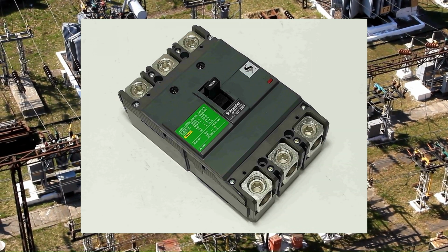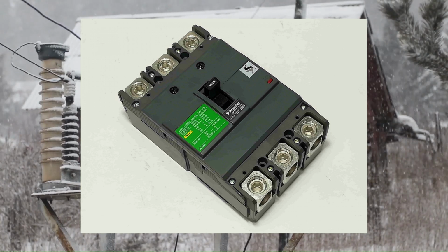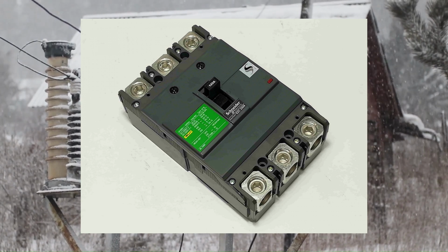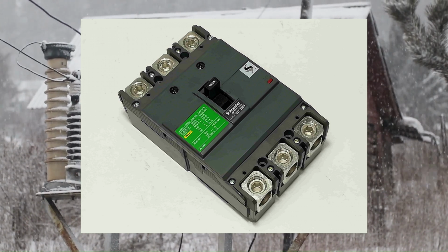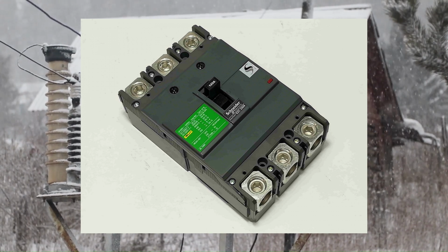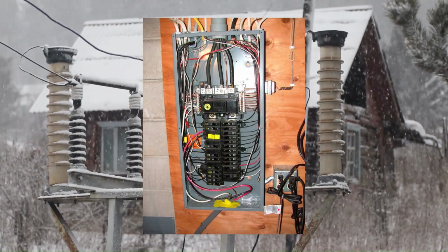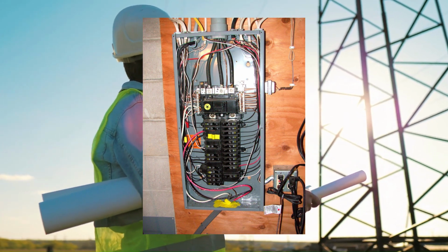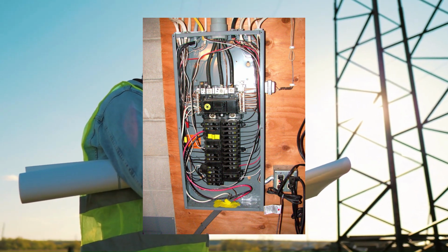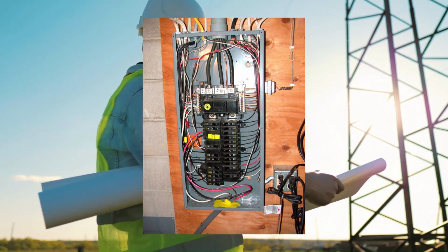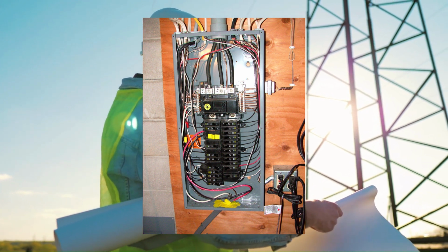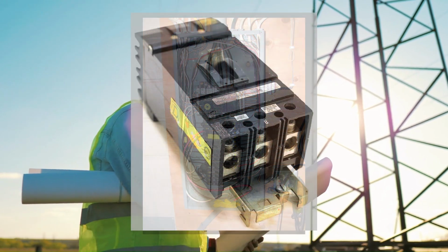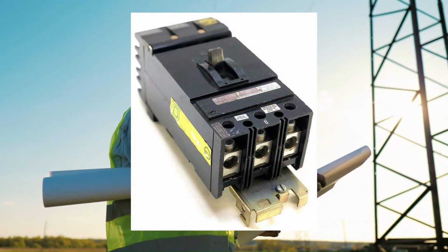The highest voltage at which a fuse or circuit breaker is intended to reliably interrupt the current is indicated by its voltage rating. The device's capacity to inhibit internal arcing, which happens when a current is opened under overcurrent or short circuit conditions, is specifically determined by the voltage rating. The voltage rating needs to be at least as high as the circuit voltage or higher. It can go up, but it can never go down. Low-voltage circuit breakers safeguard electrical circuits that are powered by less than 1000 V.